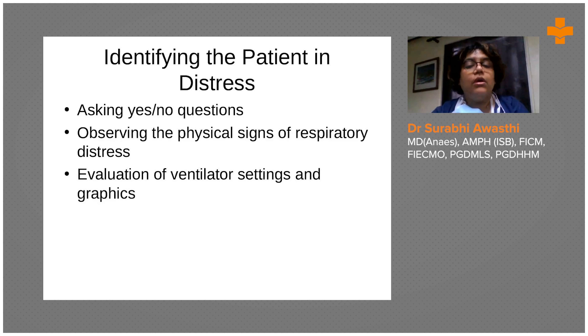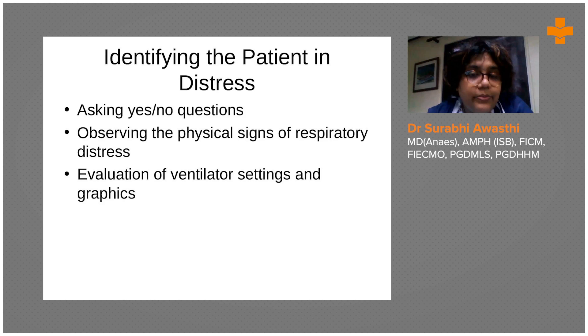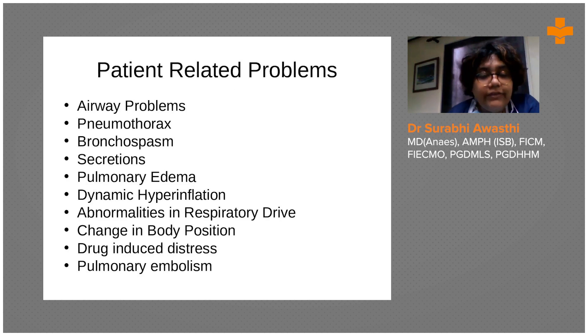After looking at the patient, you go to the ventilator and evaluate the ventilator settings and graphics. Whenever you evaluate any ventilator issue, you must go in this sequence: patient issues first, then tubing issues, and then ventilator issues. All of this is done after making sure your patient is safe first - you bag-mask him or manually ventilate him, and then you try to evaluate your patient.